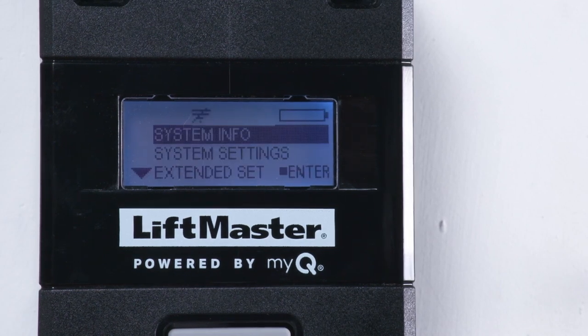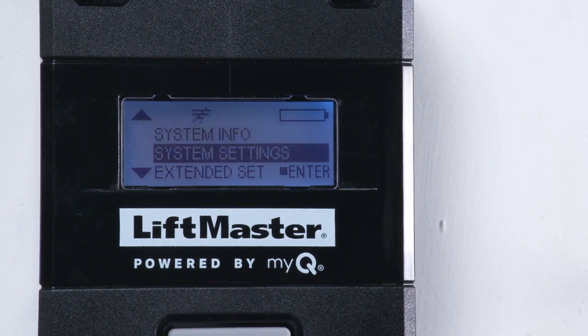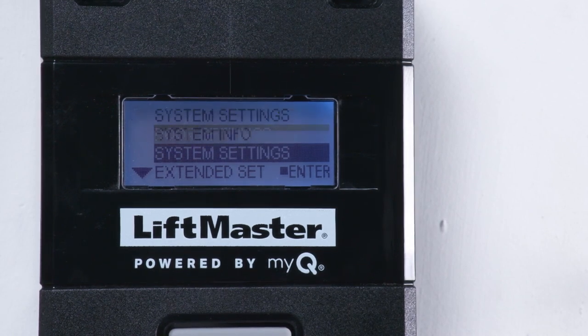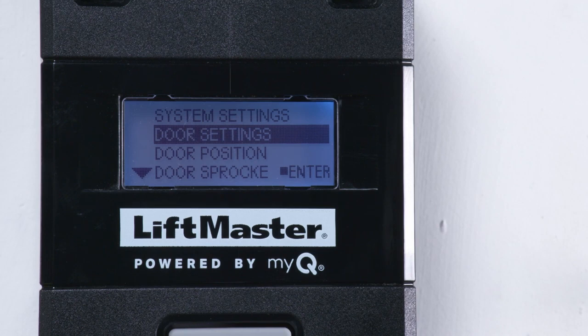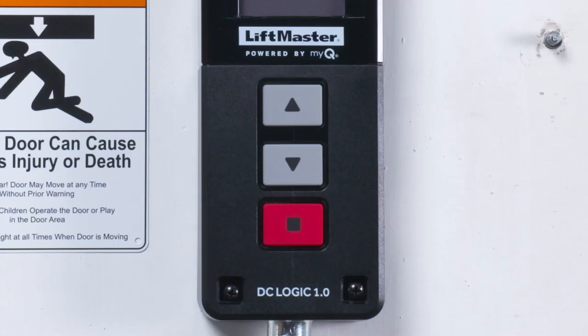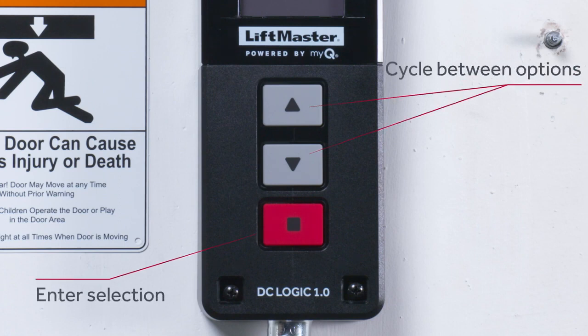It's time to program the operator. These steps are necessary to complete the setup before using the operator. When the operator is powered on out of the box or after a factory reset, the wall controller will display the Quick Start Commissioning menu. This first-time setup menu will guide you through each option that needs to be configured. To navigate through the programming menu, use the up arrow and down arrow buttons to cycle between the options.